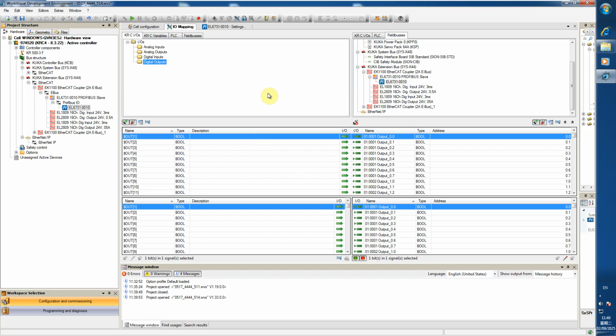Don't forget, if the robot is the last Profibus station, pay attention to the DIP switch for the Profibus position, on or off position. Remember, very important for Profibus communication, the DIP switch. If the robot is at the last station, you have to turn it on.